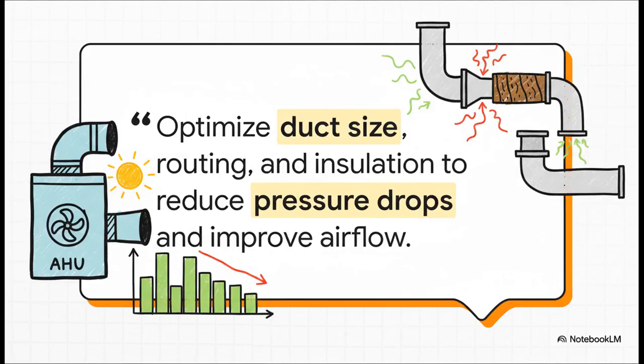And you always have to remember, the AHU doesn't work in a vacuum. The design of the ductwork is just as important as the unit itself. By optimizing your ducts, you reduce that static pressure we talked about earlier, which lets the fan run more efficiently, and that saves energy and money over the entire life of the building.